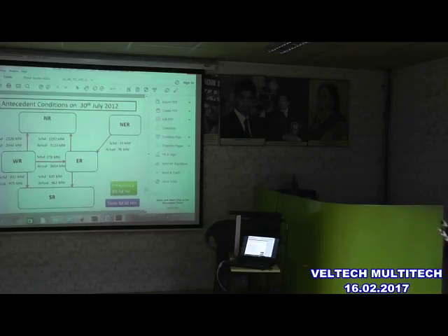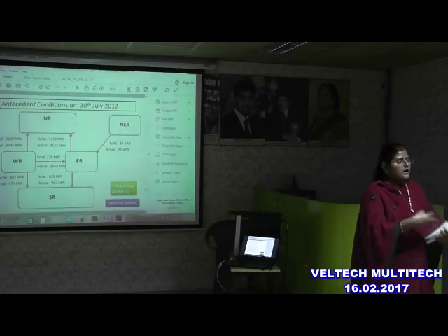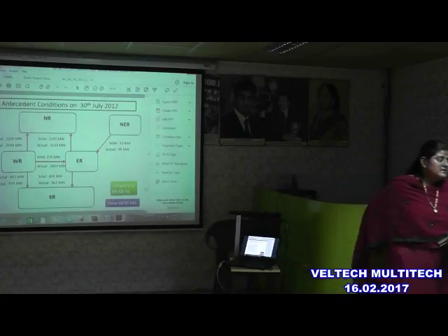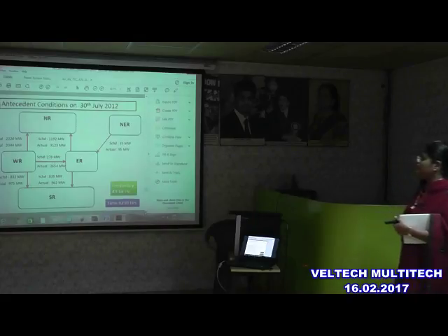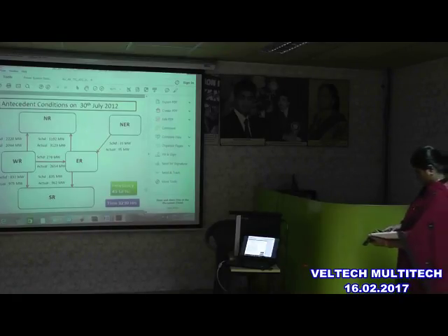This happened in 2012, after which we were tied together. During that time, we were not tied across the four regions. Which are the four regions? Northern, Eastern, Western, and Southern. So this happened at what time? Exactly, it happened at mid-time, 2:30 hours. So what was the frequency prevailing at that time? 49.68 hertz.